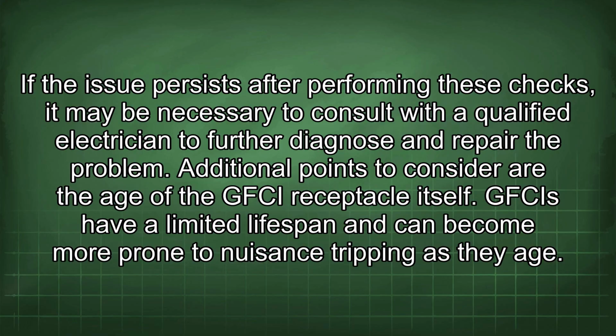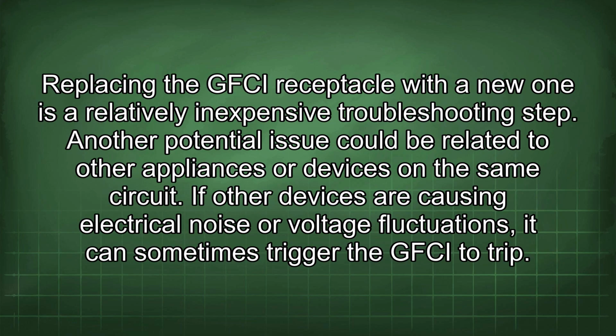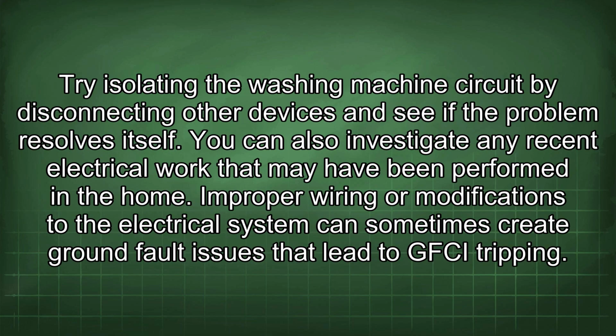Additional points to consider are the age of the GFCI receptacle itself. GFCIs have a limited lifespan and can become more prone to nuisance tripping as they age. Replacing the GFCI receptacle with a new one is a relatively inexpensive troubleshooting step. Another potential issue could be related to other appliances or devices on the same circuit. If other devices are causing electrical noise or voltage fluctuations, it can sometimes trigger the GFCI to trip. Try isolating the washing machine circuit by disconnecting other devices and see if the problem resolves itself.